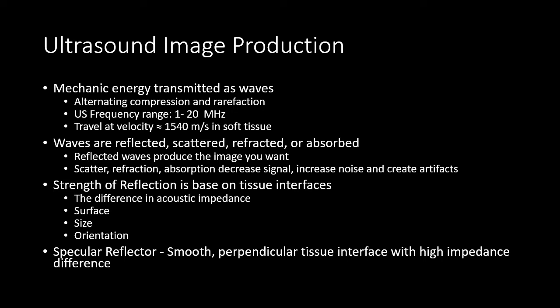The strength of a reflection off of a tissue interface is based on a few different basic factors: the acoustic impedance, or the difference in the way the wave travels through two different adjacent tissue types; the surface of that tissue interface and whether it's very smooth or irregular; the size of that tissue interface, whether it's a large uniform interface or a small interface; and the orientation of that interface to our probe — whether it's oriented perpendicular to the probe and thereby a strong reflector, or oriented parallel to our ultrasound wave and therefore a poor reflector.